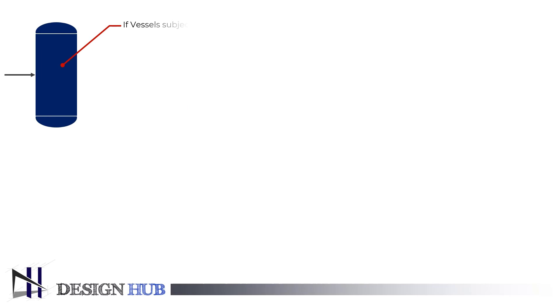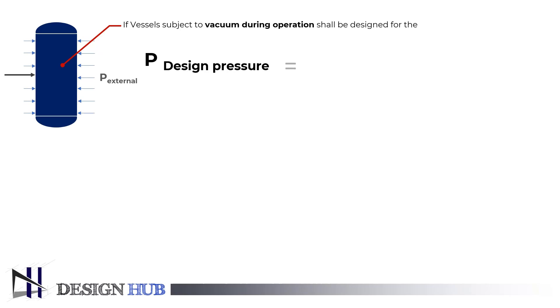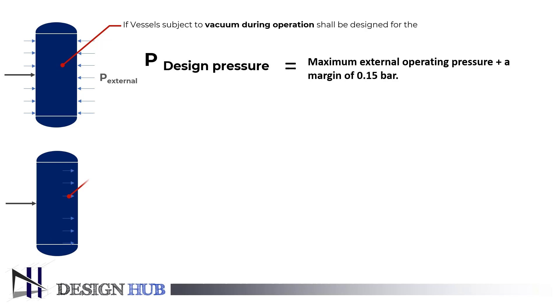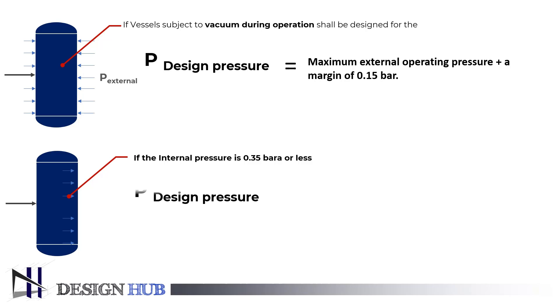Now we will see for vacuum condition: if vessels are subject to vacuum during operation, they shall be designed for the maximum external operating pressure plus a margin of 0.15 bar. If the internal vessel pressure is 0.35 bar or less, then the vessel will be designed for full vacuum condition.